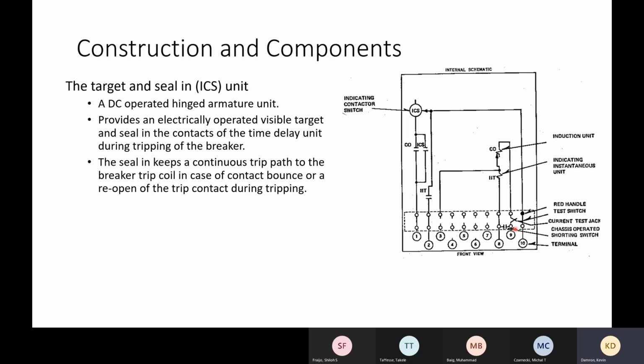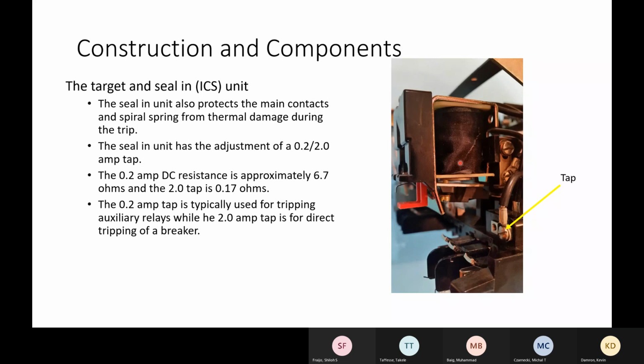So you can see, 8 and 9 here is for that. And then if these operate, they come over here and close either my instantaneous or my seal-in. And then if I go terminals 1 to 2, I take that into my DC circuit. And if you look back at the first drawings that we talked about, you'll find those same terminals. The one other thing that a lot of them have is a target seal-in, and they're either 0.2 or 2 amp devices. It depends on what voltage you're using them at typically, and which one you want to use.